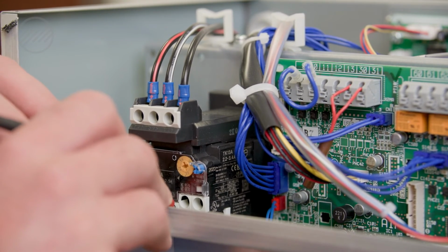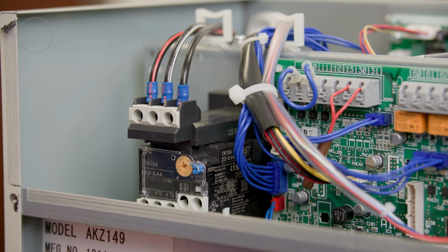If proper voltage is being supplied, next step would be to check your plumbing to ensure there are no blockages or obstructions. And then also, if your oil viscosity is correct and not too heavy, the pump and motor are probably bad.